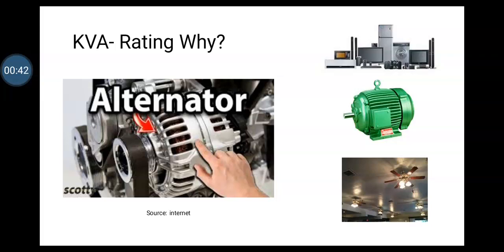According to the load, the power factor varies. For example, for a resistive load the power factor will be unity, for an inductive load it will be lagging, and if it is a capacitive load, it will be a leading power factor. Now the alternator, or the manufacturer, doesn't know what kind of load the customer is going to use, and also doesn't know what kind of power factor is going to be fed to the alternator.